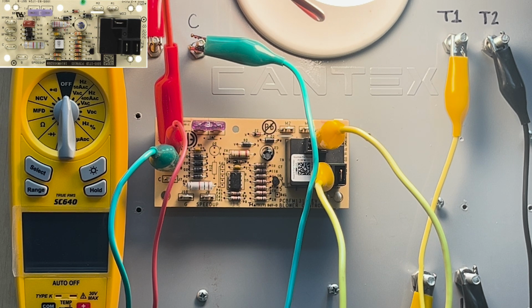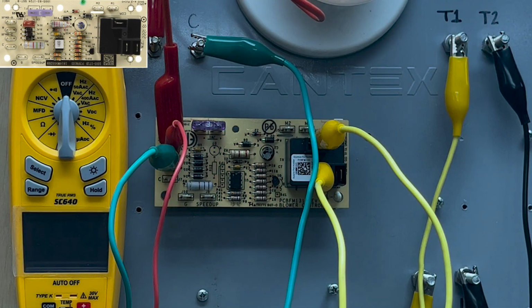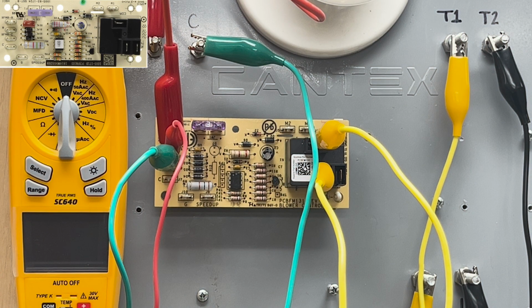So we're just trying to get more efficiency out of the unit, because we are still transferring heat. We're removing moisture at a higher efficiency, because within that 60 seconds, the only thing running between the compressor and the blower is the blower. So look at what it costs every time this thing comes on and off within a year's time, how much more comfort are you giving your home at just the cost of a fan motor running for 60 seconds?